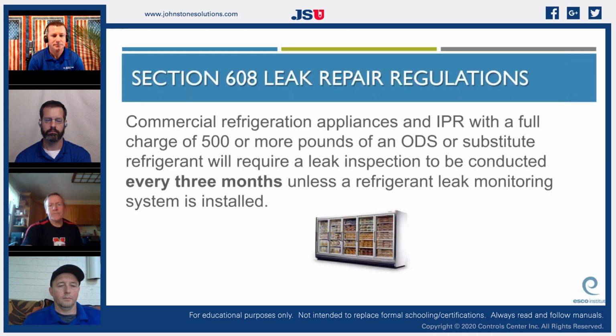So don't overthink it. The ones Clifton was just talking about, with 500 pounds or more of ozone depleting substance or substitute refrigerant, require a leak inspection to be conducted every 3 months. So basically, I guess you're going in and calculating the leak rate every 3 months, and doing an entire leak inspection. And remember, that's a leak inspection. That's a lot of work.